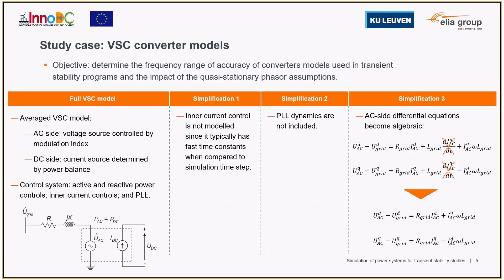Here we show an example analyzing the accuracy of VSC models using transient stability programs and the impact of simplifying assumptions. The VSC model used was an average model, and the control loops included were the active and reactive power controls, the inner current control, and the PLL. From this model, it was possible to identify three simplifications typically adopted in transient stability programs.